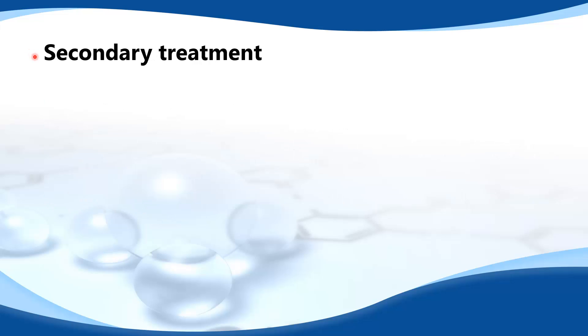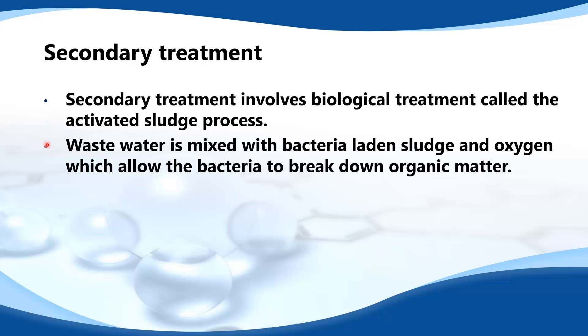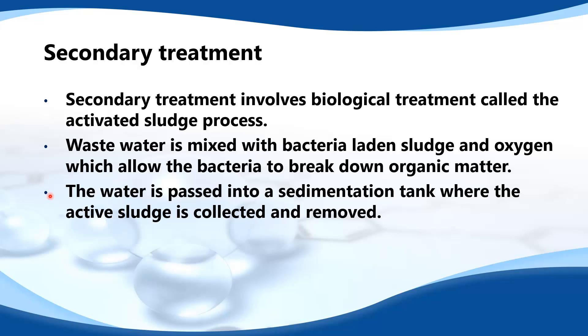Next we look at secondary treatment. Secondary treatment involves biological treatment called the activated sludge process. Wastewater is mixed with bacteria-laden sludge and oxygen, which allows the bacteria to break down organic matter. The water is then passed into a sedimentation tank where the active sludge is collected and removed.